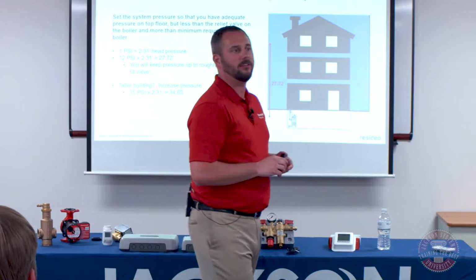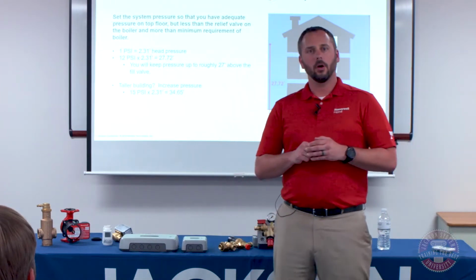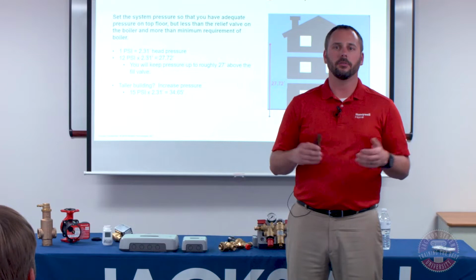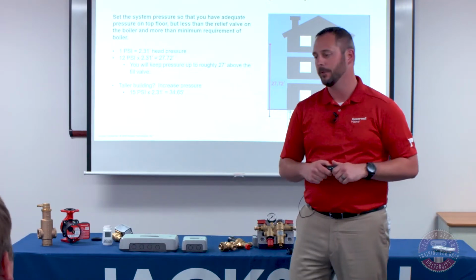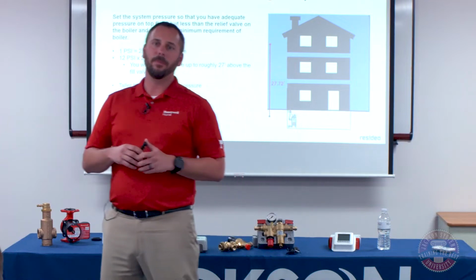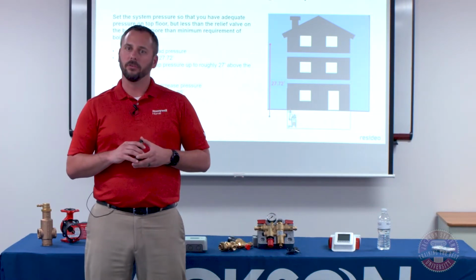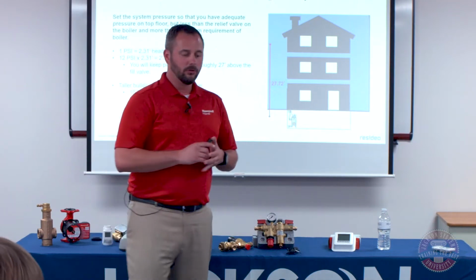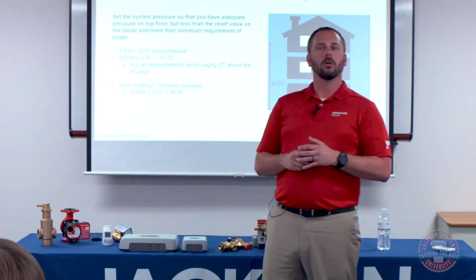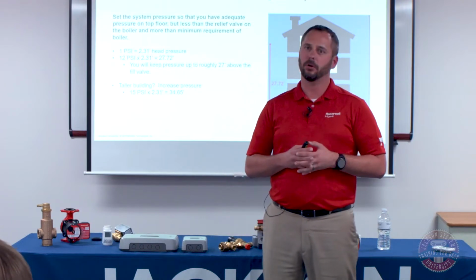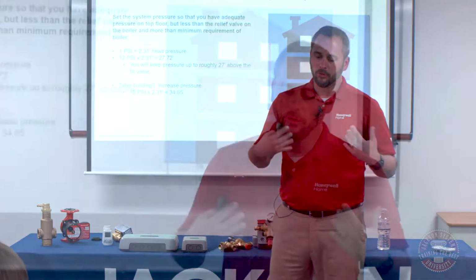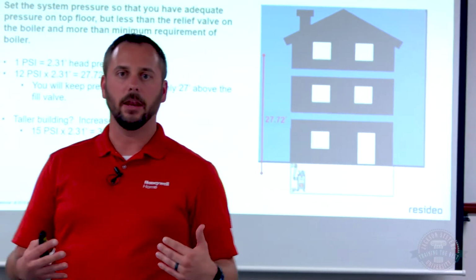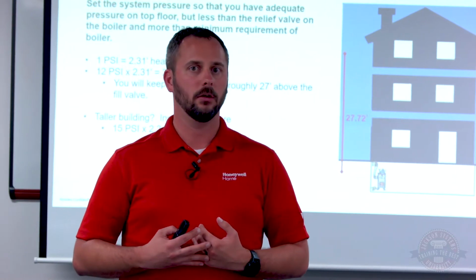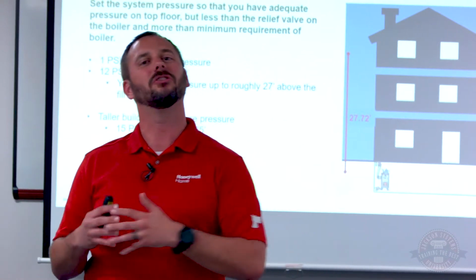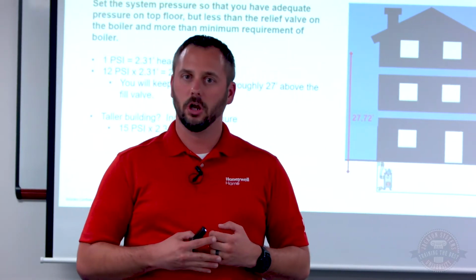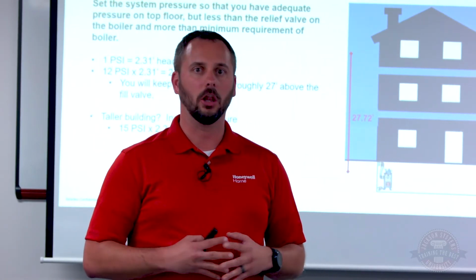Now when we talk about sizing the fill valve, the old industry standard that I had mentioned used to just be 12 pounds. Our expansion tanks are still sized at 12 pounds, which I'll show in a minute. But 12 pounds was based on the average home that was installed whenever they made that decision. So in our hydronic heating world, we typically use PSI for the static pressure, and then we measure our pumps in feet of head. So 1 PSI is equal to 2.31 feet of head. That's a formula you're going to want to know and understand because that comes up in our world a lot.